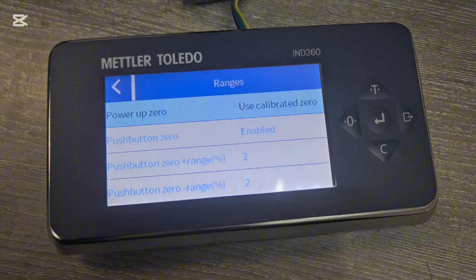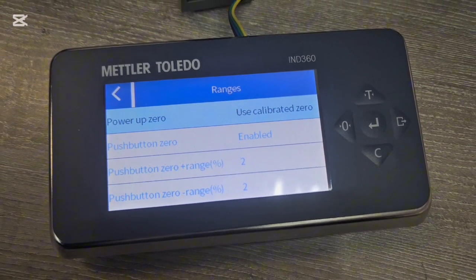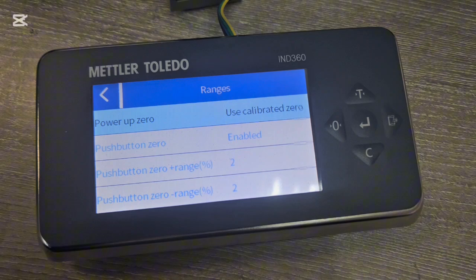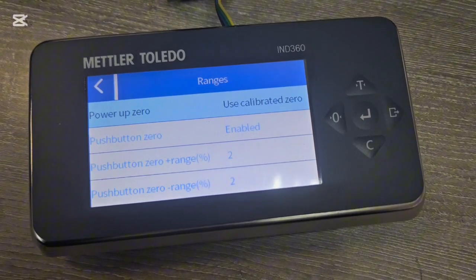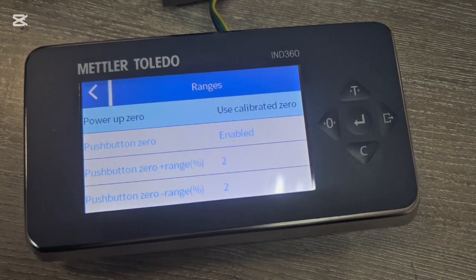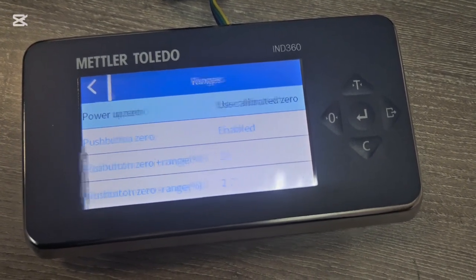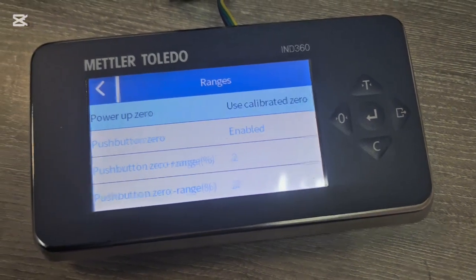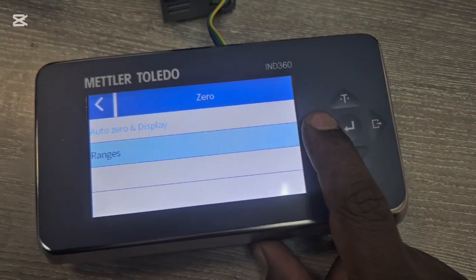Under Pushbutton Zero Range you can set a percentage. Currently the scale is set to 2%, meaning you cannot zero the scale if it's showing a value greater than 2% of full range. My full range is 0 to 150, so 2% of 150 is 3 kg — meaning I can zero the scale if it's within plus or minus 3 kg, but not beyond that.